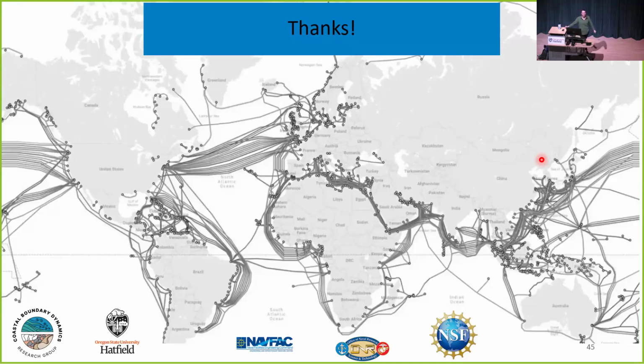That's a great question. I was very worried about cable burial. I was out there every day looking for my cable to see if it was exposed. The cable we were using has a fair amount of metal protection inside of it, and it's intentionally weighted to have a greater density than the sand-water matrix. So it's designed basically to self-bury in the sand.